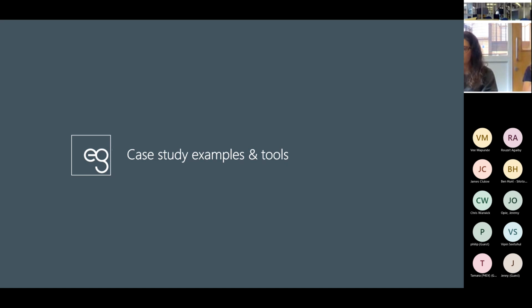Oh, so formative evaluation. In formative evaluation, you don't necessarily need to test in a simulated environment. I mean, you could do, but it's not always necessary, because what you're looking for is an early indication on the user interaction to provide input into the design. I guess it's one of those things you might want to evaluate on a case-by-case basis in terms of how critical the use environment might be in terms of influencing the safety and efficacy of use. But it's definitely something you need to do as a part of summative evaluation. So sometimes you need to be a bit pragmatic about these things. So often in formative evaluation, they're not done in a simulated use environment, if that answers the question.